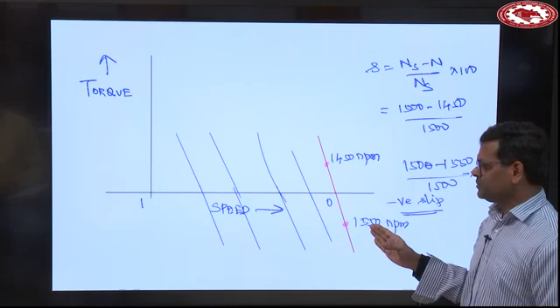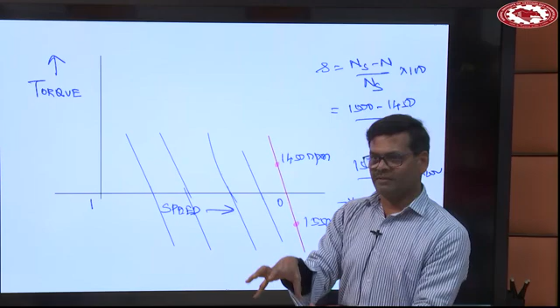But the requirement is the speed of the rotor should be greater than the speed of the magnetic field, because we want power flow to happen from rotor to stator. So the speed of the magnetic field should be here, meaning it cannot be directly connected to the grid, because grid frequency is 50 hertz, 120f by p, it is always 1500 rpm, it is fixed. So therefore you will have to put a power electronic converter.